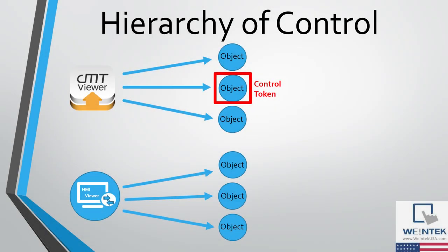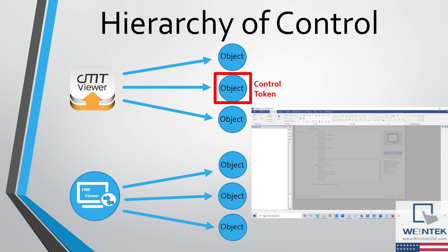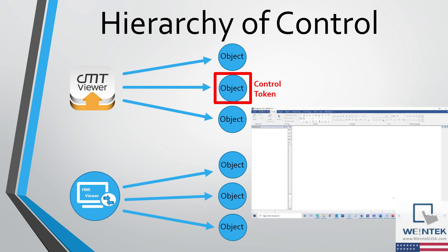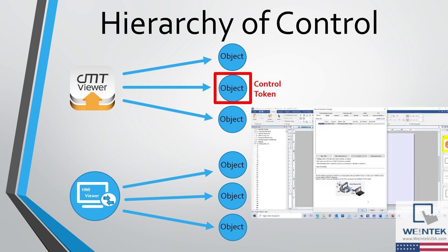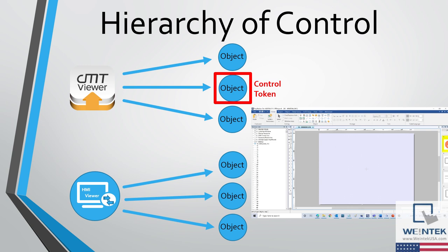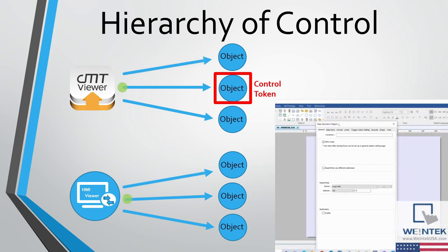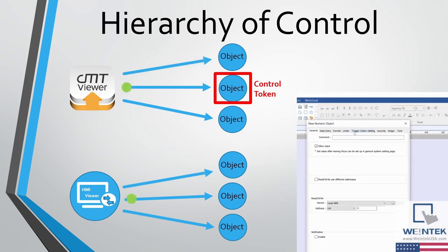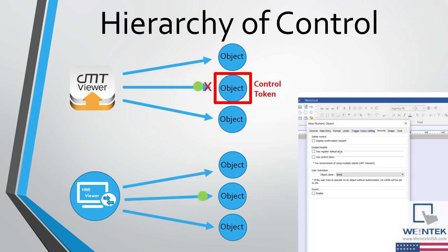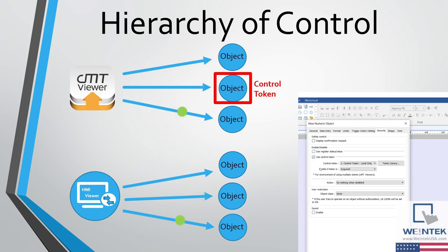However, unlike CMT Viewer, HMI Viewer does not have a way of establishing a hierarchy of control. Whereas CMT projects can use control tokens to determine what objects can be controlled by those connecting through CMT Viewer, HMI Viewer cannot. Therefore, users will have to be careful not to put the operator at risk when connecting to an HMI.